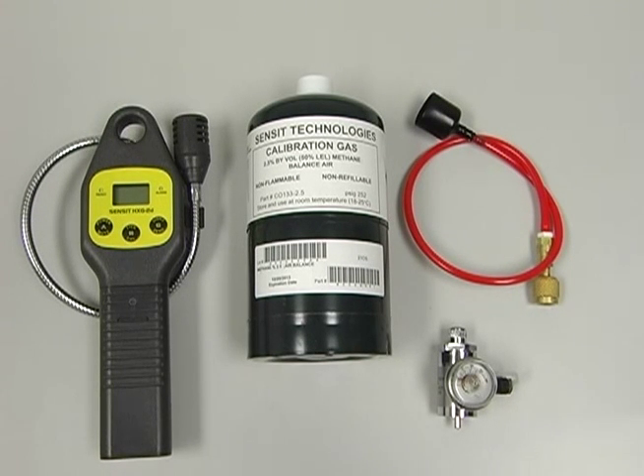HXG2D calibration. In order to calibrate the HXG2D we will require the HXG2D itself, a cylinder of 2.5% methane or 50% LEL methane, a red calibration hose assembly, and the regulator assembly.